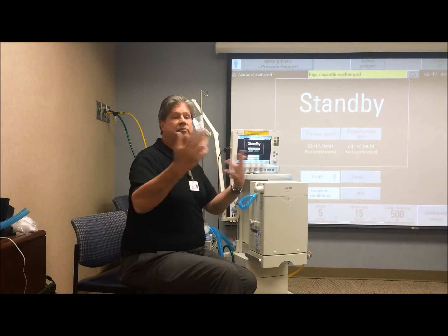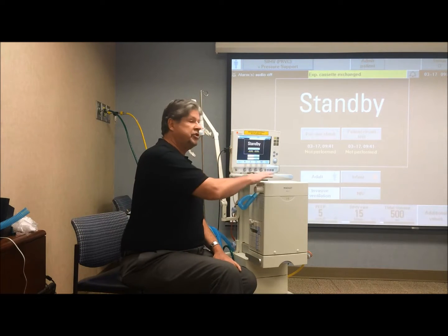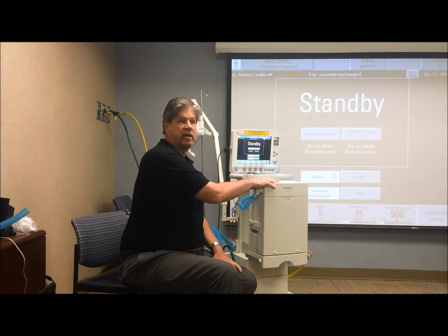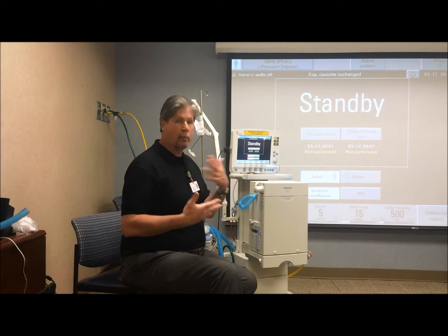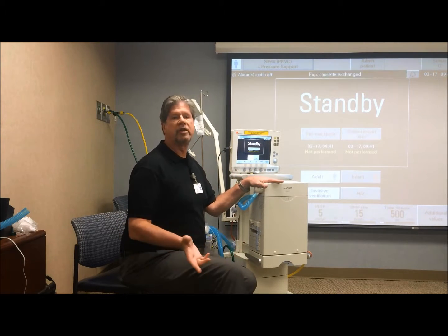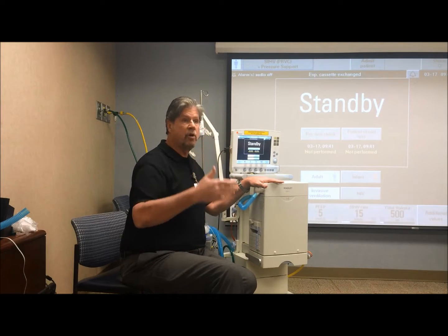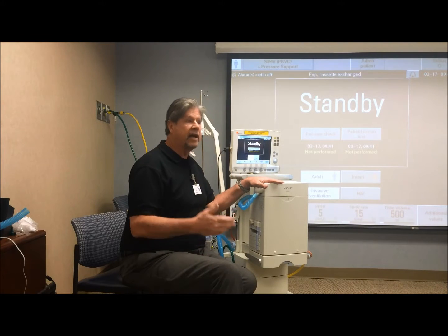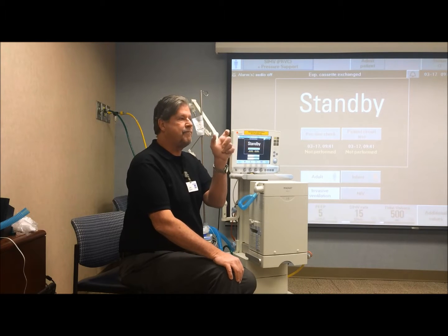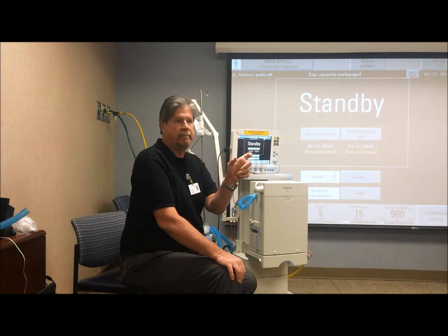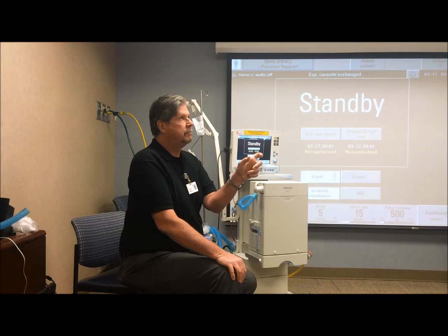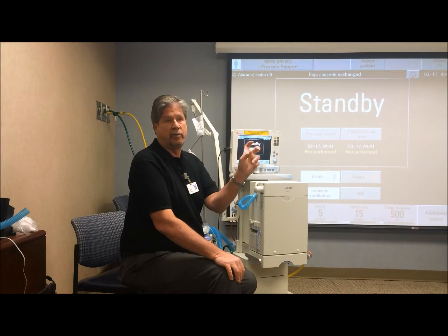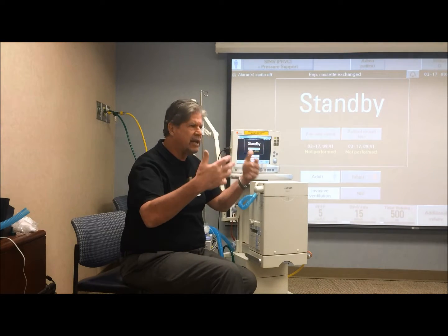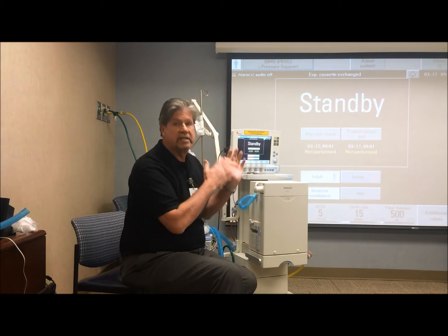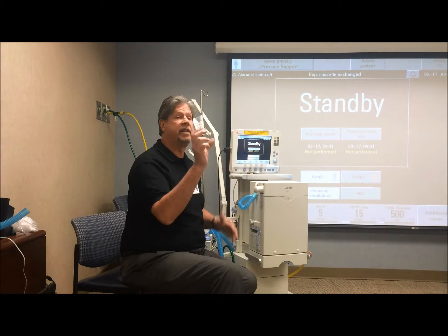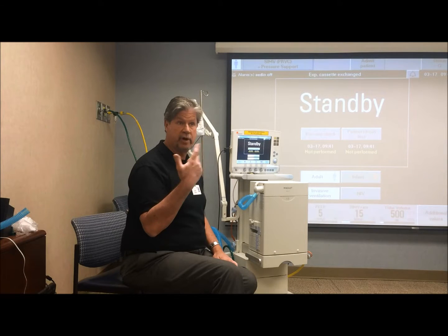telling the subsequent users that you weren't able to officially calibrate the cassette, but the ventilator will work properly, assuming that there's nothing wrong with the cassette. You can still go through a complete pre-use check, but you will still get a message that says not performed on the pre-use check, and it will have calibrated everything else except the cassette and the O2 cell, right, because it didn't have O2 and air.